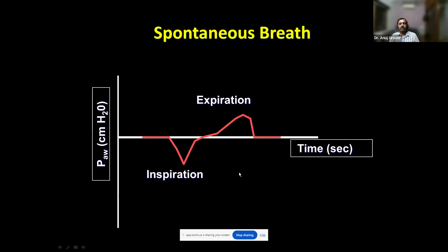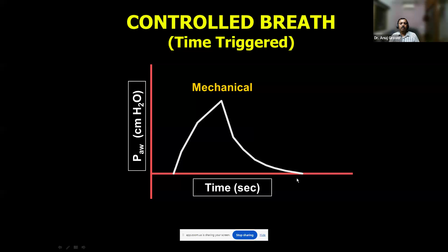How does the pressure waveform look in a spontaneous breath? So there is a negative deflection, okay, because the baby takes an inspiration, and at the end the baby expires. There's a positive deflection, which is reverse of the control breath. In the control breath, there's a positive flow towards the baby in the mechanical breath and away from the baby in the expiration.